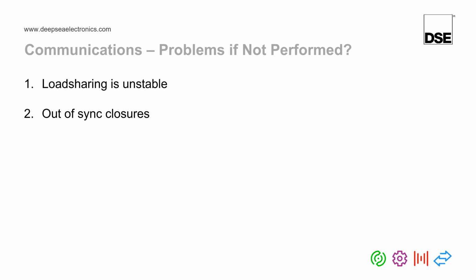Another question has just come in: do we have to connect two 120 ohm resistors even if we only have two gensets? That is correct. If you have two gensets, 5 gensets, 32 gensets, it does not matter. You must have a 120 ohm termination resistor at the start of the MSC cable and at the end of the MSC cable. If you only have one generator on its own, you can leave the MSC terminals completely disconnected.